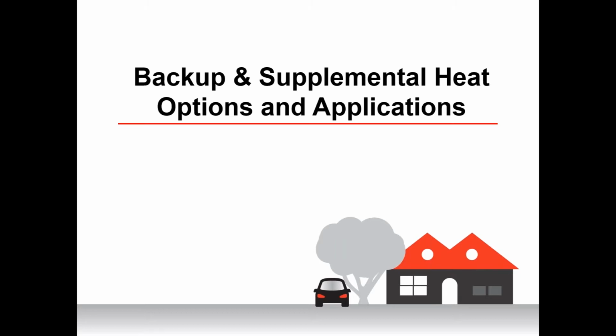But when do we need backup or supplemental heat? Climate is the number one reason. While cold climate heat pumps have tremendous heat output, even at sub-zero temperatures, as we saw in the earlier slides, there are climates where it gets too cold for heat pumps to be a sole source of heat, no matter how good we are as a cold climate heat pump. Think about Minnesota, Wisconsin, Northern Michigan, the Dakotas, and others. Backup heat is needed in these areas. It's just required. It gets too cold.